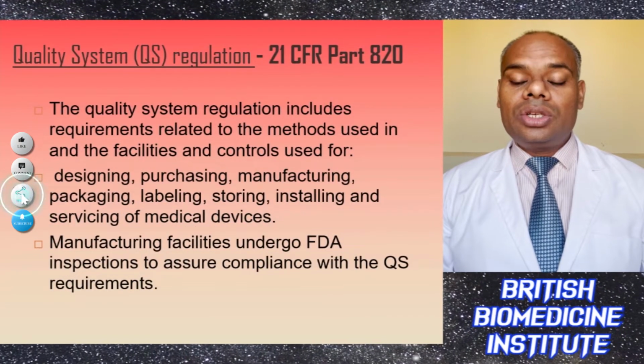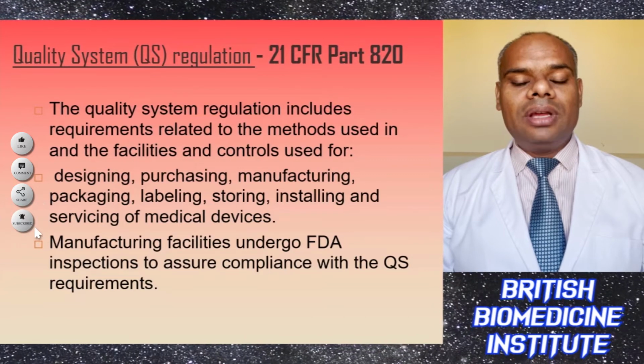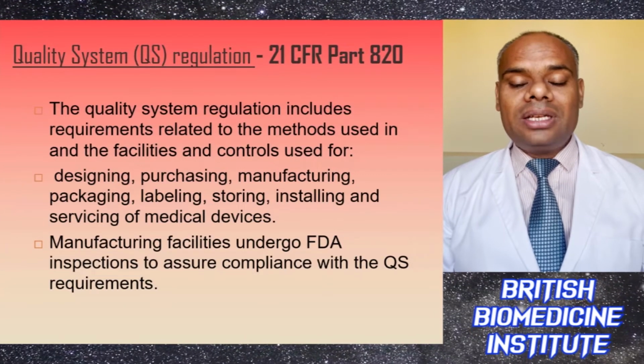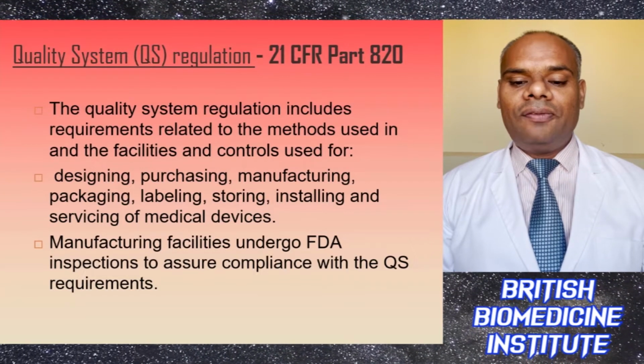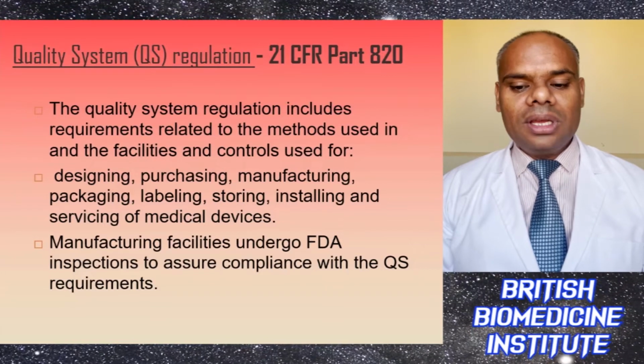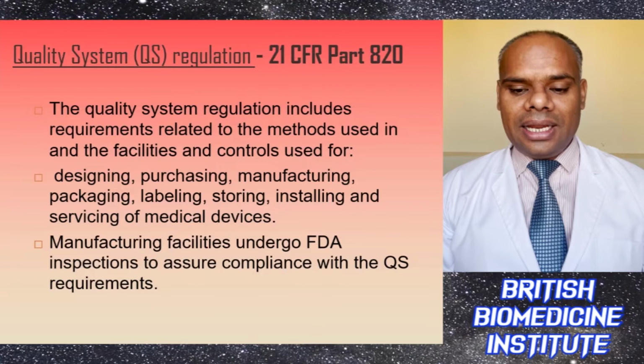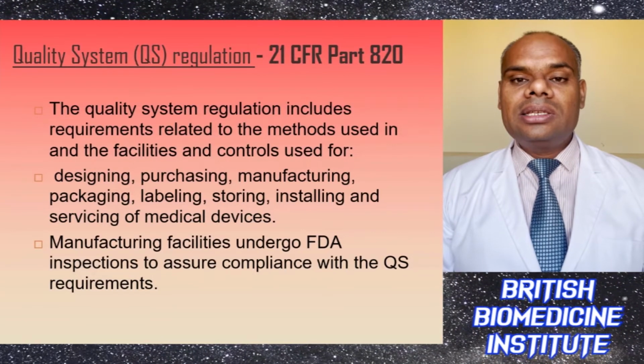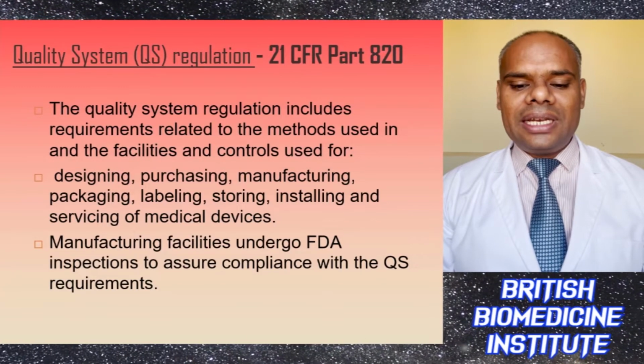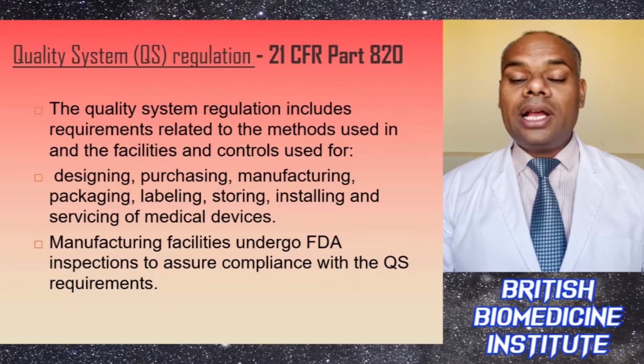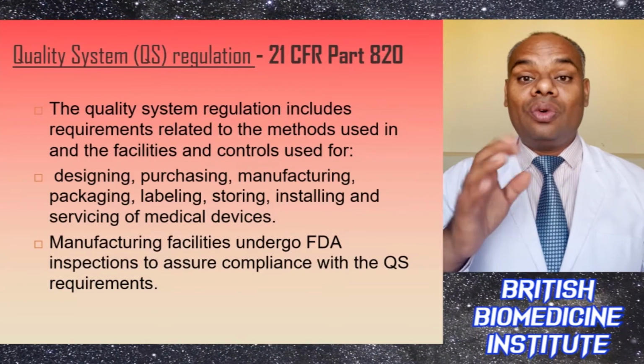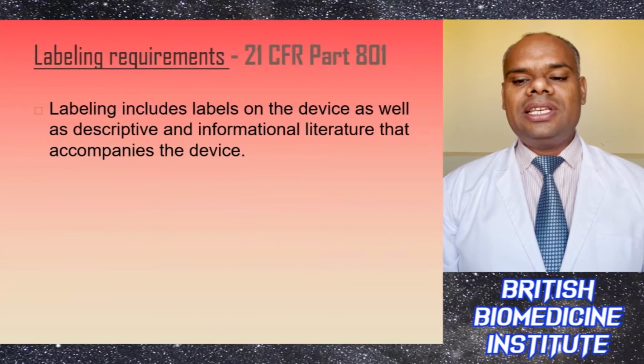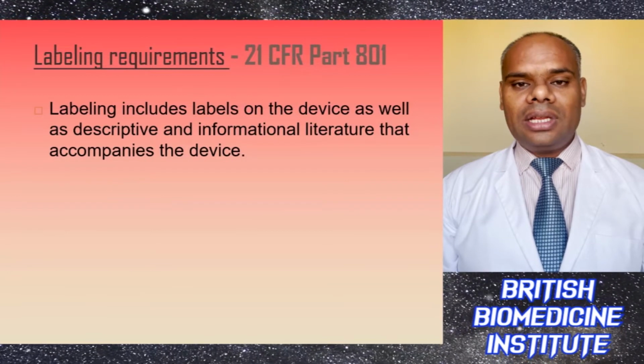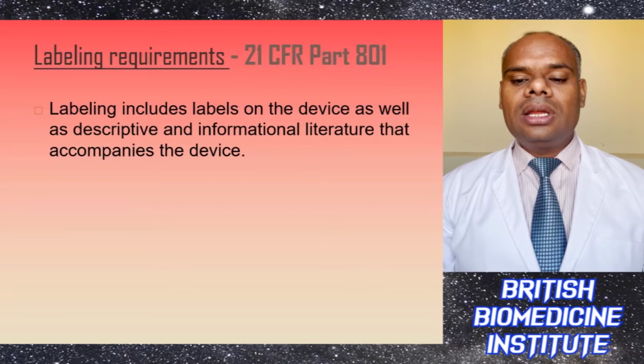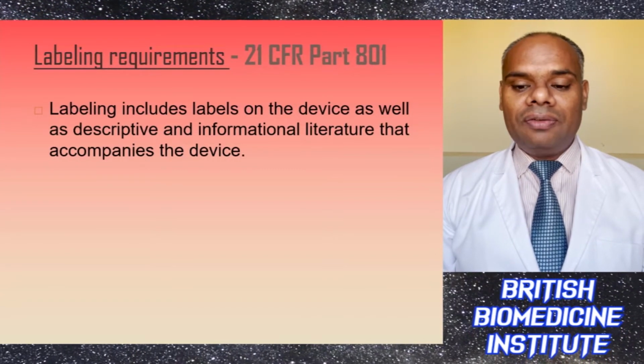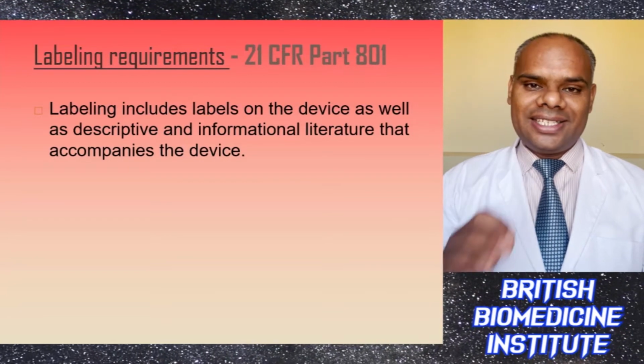So in accordance with 21 CFR Part 820, the quality system regulations basically include requirements related to the methods used in, and the facilities or controls used for, designing, purchasing, manufacturing, packaging, labeling, storing, installing, and servicing of medical devices. Manufacturing facilities undergo FDA inspections to assure compliance with QS requirements. In accordance with 21 CFR Part 801, these are the labeling requirements. Labeling includes the label on the device as well as descriptive and informational literature that accompanies the device.